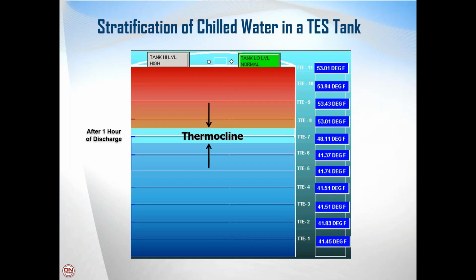Because the chilled water tank, the thermal energy storage tank, is always filled with water and is always filled with chill water. It would not be beneficial for the owner to fill and drain a chilled water thermal storage tank, because that's a costly endeavor to refill the tank and chemically treat it every time you would do that. So those two bodies of water, rainwater or stormwater retention, that would be a different type of tank. Not a different type. It could be a concrete tank like the chilled water tank, but they would be two separate tanks and just be used for two distinctly separate applications.